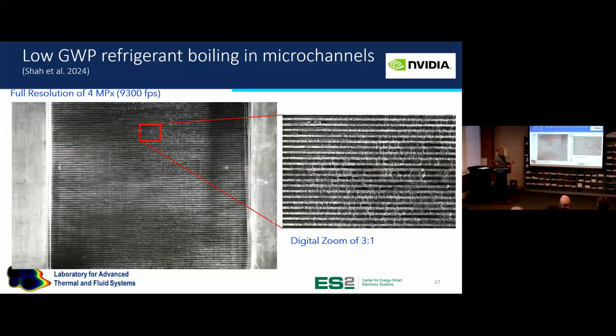That's one of the things we're working on. The real engineering challenge is how do we work on low global warming potential fluids that still do well enough as a heat transfer fluid, that still can remove heat, because these goals are contrary to each other. If you get low global warming refrigerants, generally they will not be as good at removing heat as some standard refrigerants.